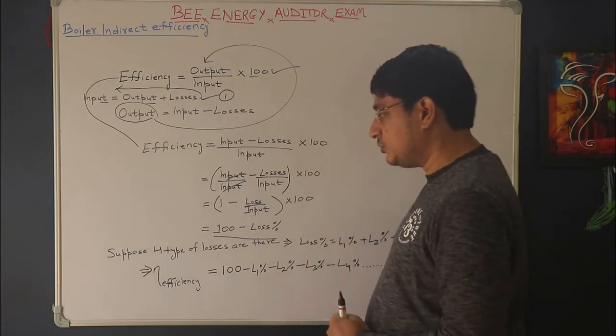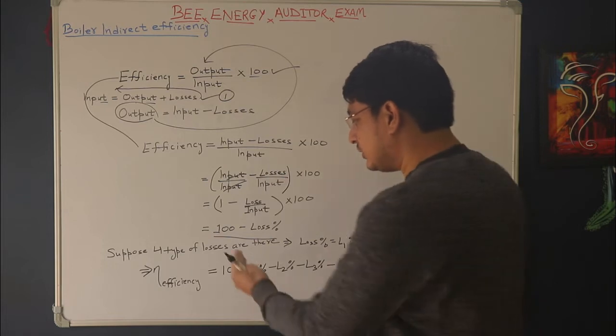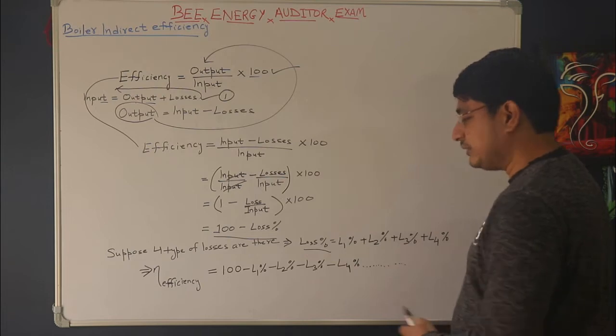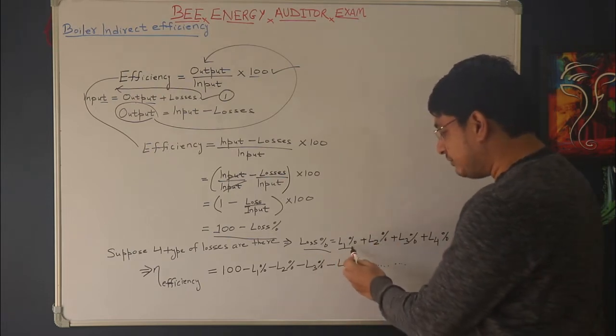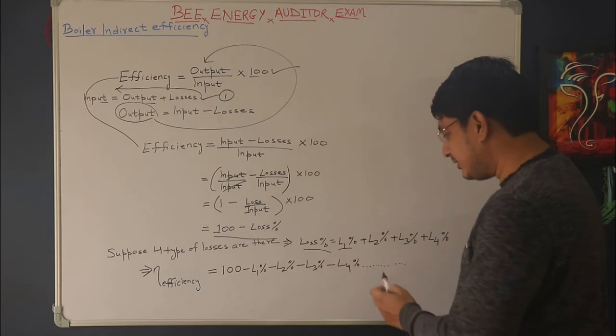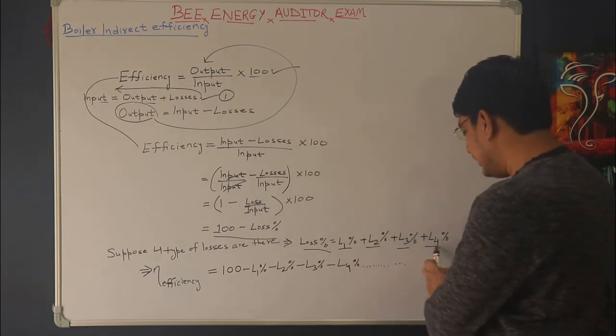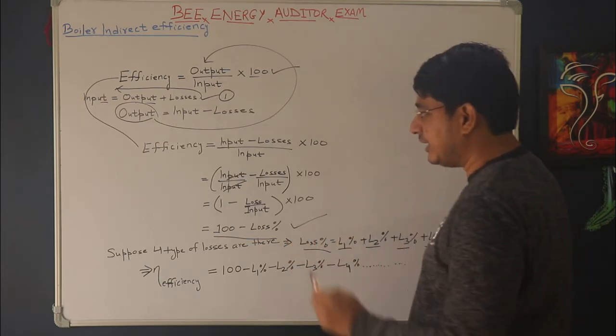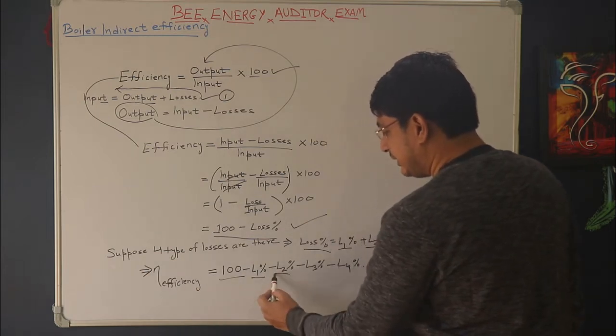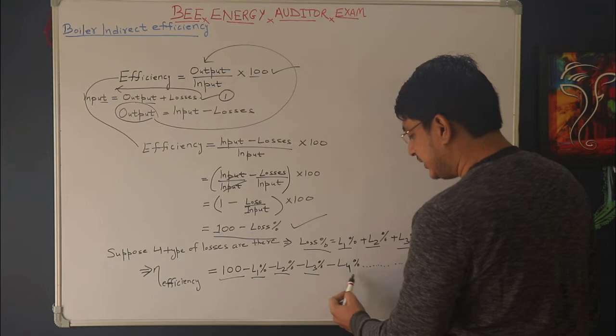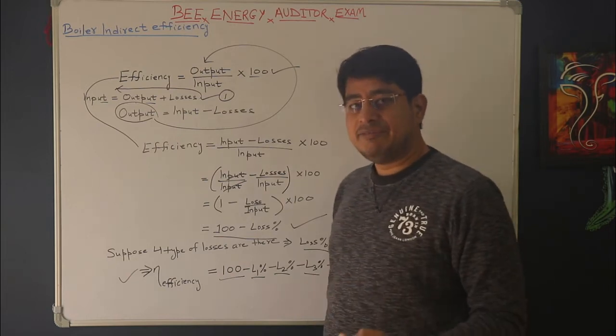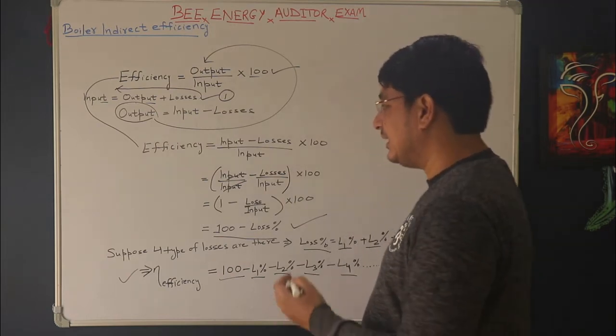Suppose there are four types of losses in my system. The total loss percent = L1% + L2% + L3% + L4%. So the efficiency formula becomes: 100 − L1% − L2% − L3% − L4%. This is the concept I will use for calculating boiler efficiency using the indirect method.